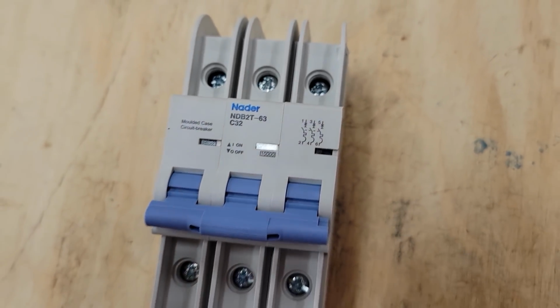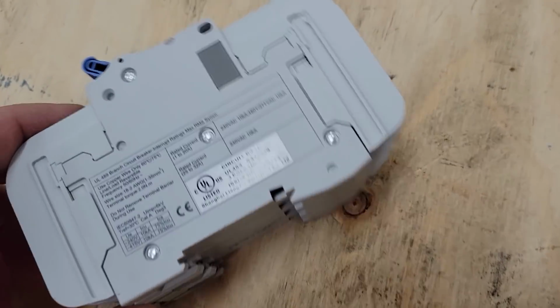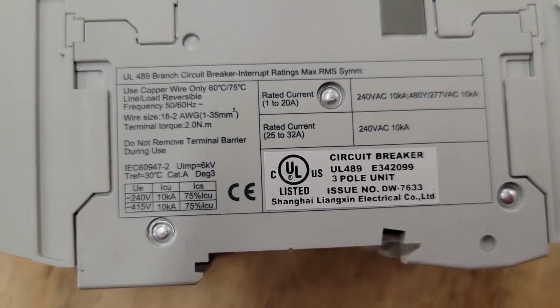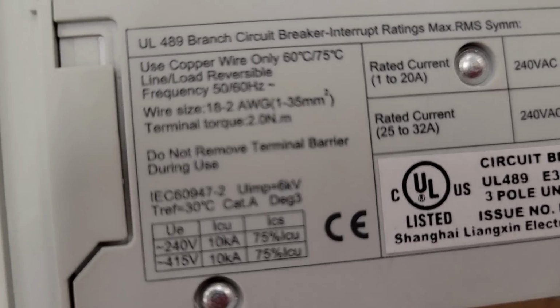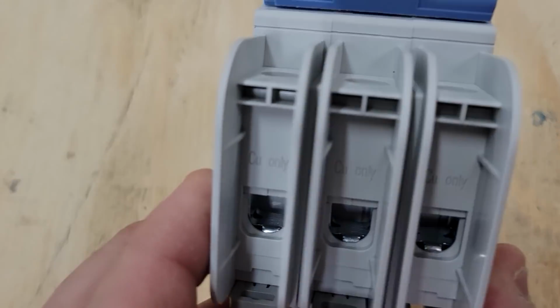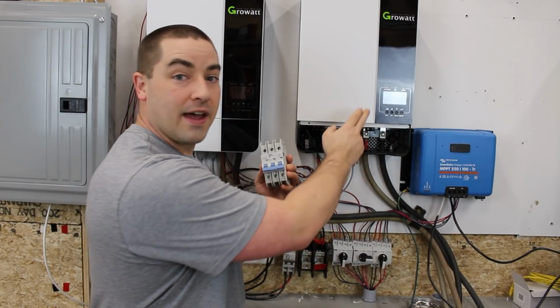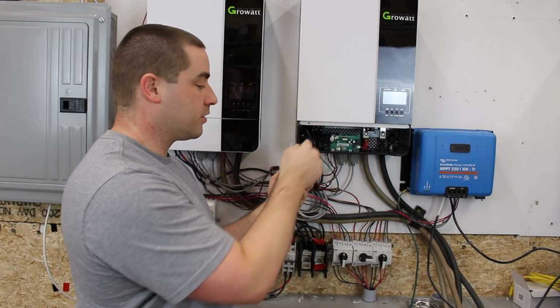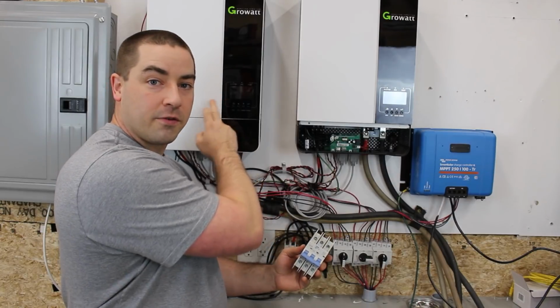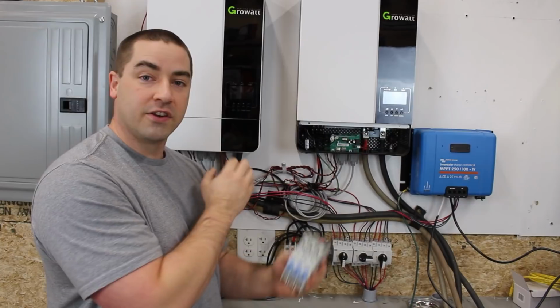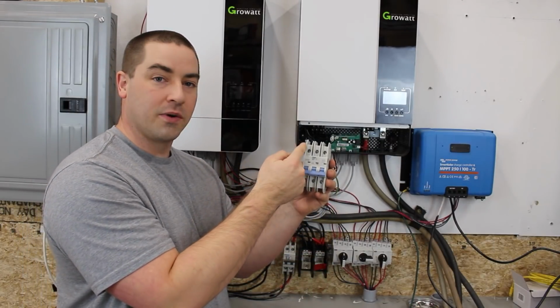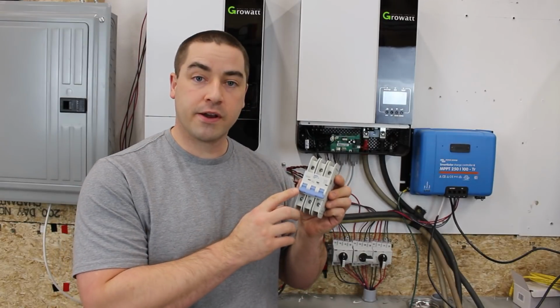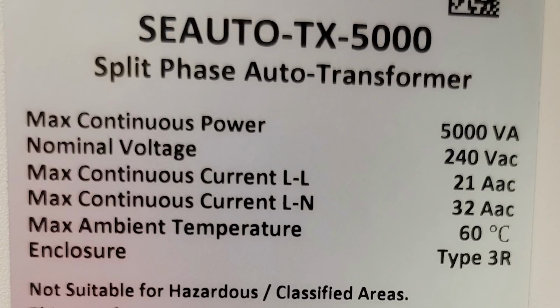This is a triple pole circuit breaker. This one happens to be Nader. It is UL, so it has the UL sticker right on the side. Each pole is 32 amps, and each pole can break 240 volts AC. So the way that I'm going to hook this up, I'm going to have L1 from inverter 2 going to one pole, L1 from inverter 1 going to another pole, and the neutral off the auto transformer going to the last pole.